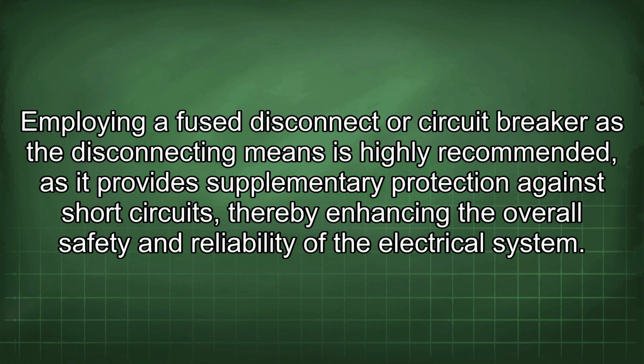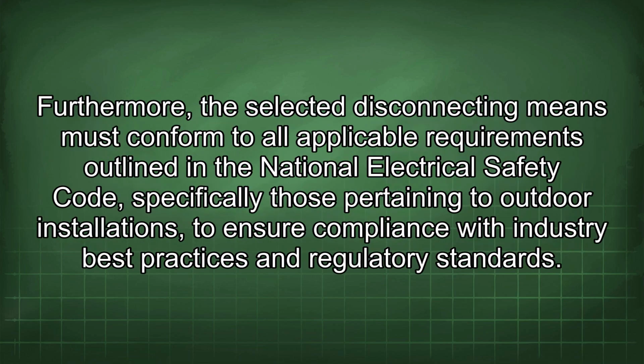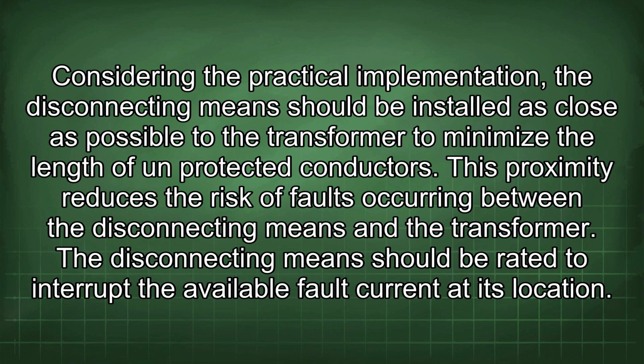Employing a fused disconnect or circuit breaker as the disconnecting means is highly recommended, as it provides supplementary protection against short circuits, thereby enhancing the overall safety and reliability of the electrical system. Furthermore, the selected disconnecting means must conform to all applicable requirements outlined in the National Electrical Safety Code, specifically those pertaining to outdoor installations, to ensure compliance with industry best practices and regulatory standards. Considering the practical implementation, the disconnecting means should be installed as close as possible to the transformer to minimize the length of unprotected conductors. This proximity reduces the risk of faults occurring between the disconnecting means and the transformer.